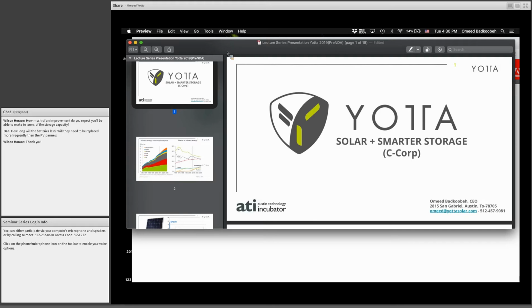13,000 cycles. So theoretically, if we use that specific cell within our product and regulate the temperature, we could theoretically have close to the full 10,000 to 13,000 cycle life of that battery within our SolarLEAF system. If you account for, say, a once-daily full cycle—meaning 100% discharge of that capacity in one full cycle day—that can equate to roughly 27 years of lifespan on that specific battery chemistry.